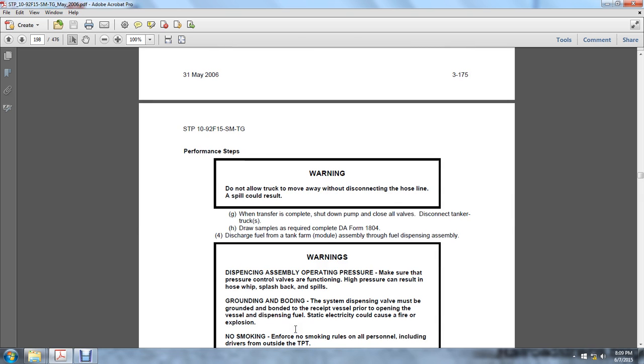Warning, do not allow the truck to move away without disconnecting the hose, as a spill could result. When transferring is complete, shut down the pump, close all the valves, and disconnect the tanker truck. Draw the sample that was required to complete the DA Form 1804, then discharge fuel from the tank farm module assembly through the fuel dispensing assembly.